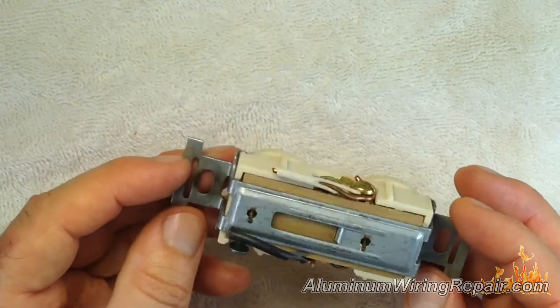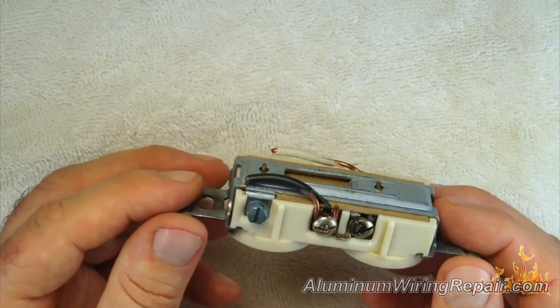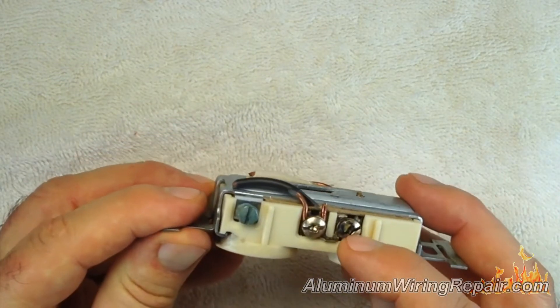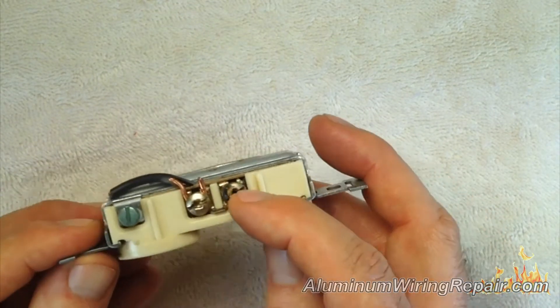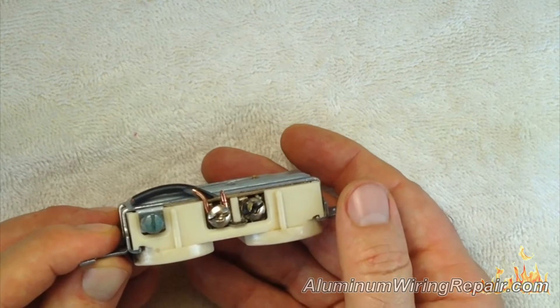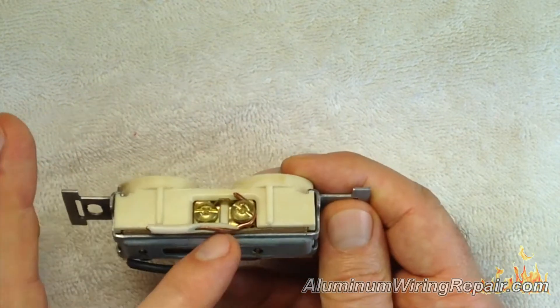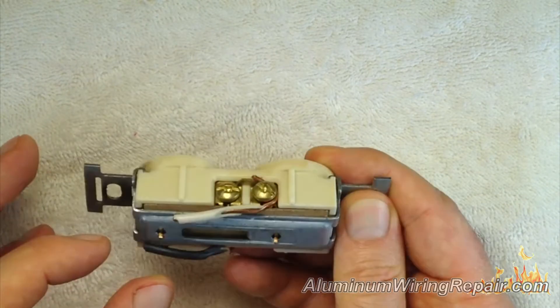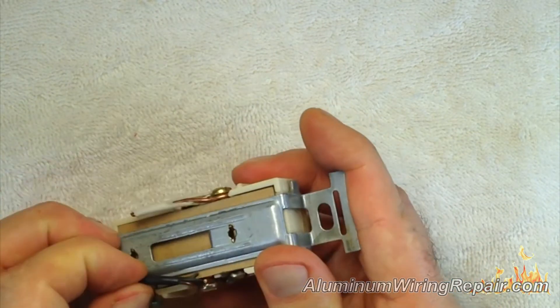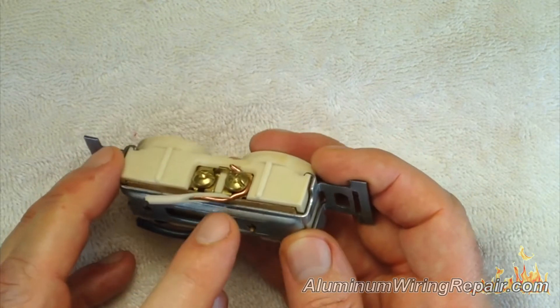This one here I'm going to show just because it isn't aluminum, but it was installed by an amateur electrician. You can see what looks like arcing happening on the outside of the screw. This is actually a copper installation and this is the end of a particular circuit — as you can see there are only two wires.